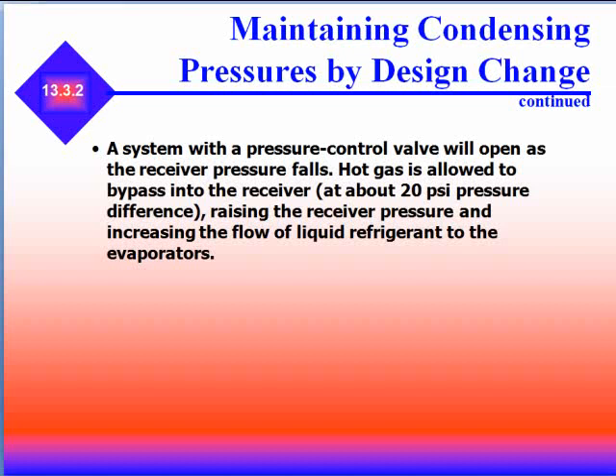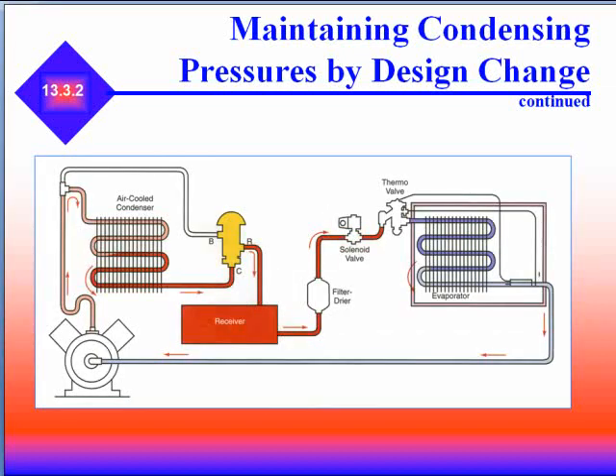A system with a pressure control valve will open as the receiver pressure falls. Hot gas is allowed to bypass into the receiver at about 20 PSI pressure difference, raising the receiver pressure and increasing the flow of liquid refrigerant to the evaporators. This is an example of the hot gas version of pressure control. Notice the solenoid valve for the pump-down system, and notice the yellow bypass valve that allows hot gas out of the discharge line — prior to the air-cooled condenser — to move into the receiver if needed.